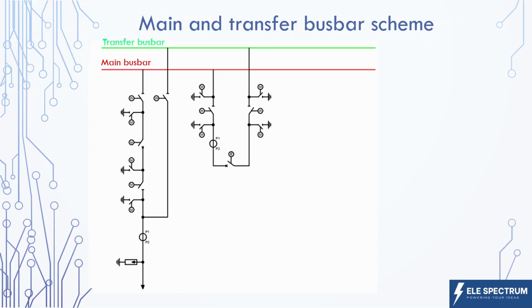However, if the potential on both sides of the disconnector is the same, then we are still able to switch this disconnector because the potential on both sides is the same. And for this kind of operation, we need a special type of disconnector which has bus transfer capability. If this is clear, then let's see how to do this. Let us consider that this feeder is connected to the main bus bar and the circuit breaker is on. That means the potential on this side of the disconnector is the same as the main bus bar. And to switch on this disconnector, we need to have the same potential on this side as well. To do this, we need to switch on this transfer bus coupler bay so that we will have the same potential on both sides of the disconnector and we can switch it on.